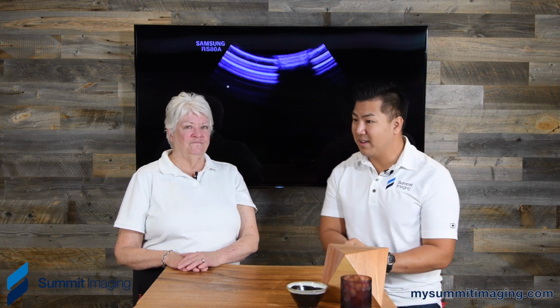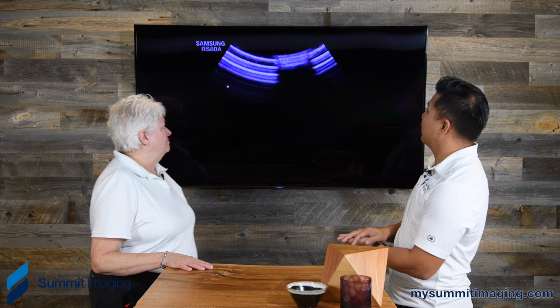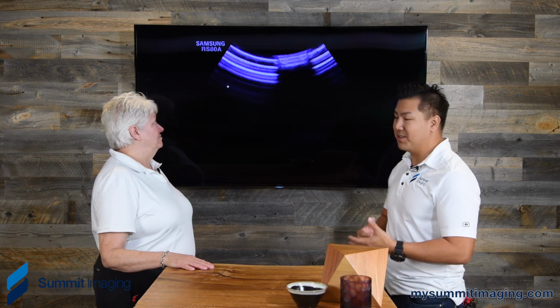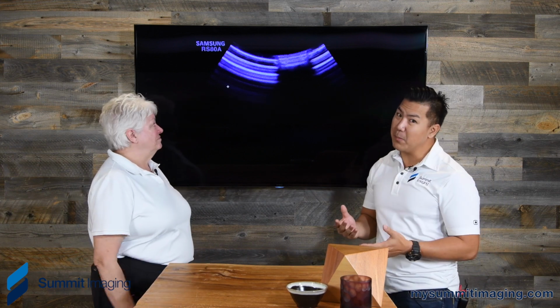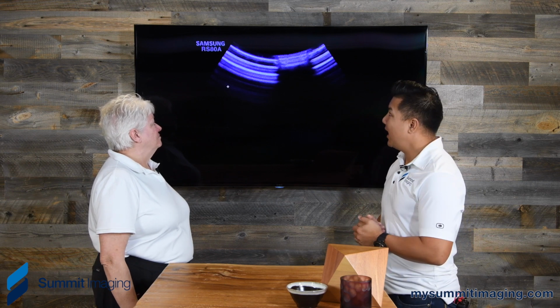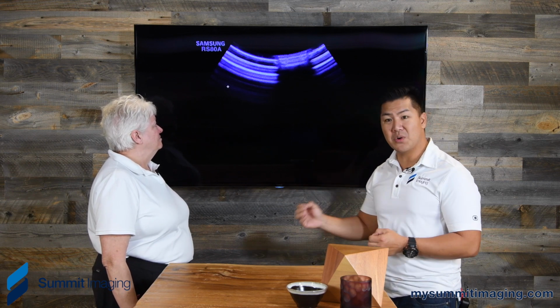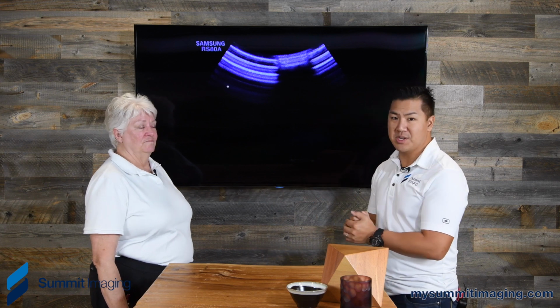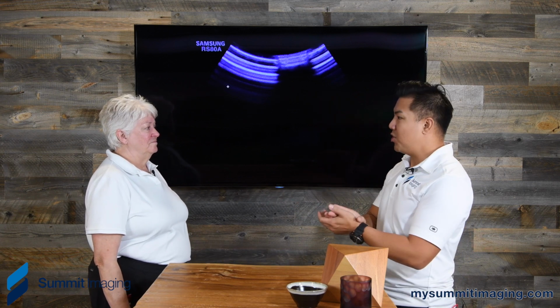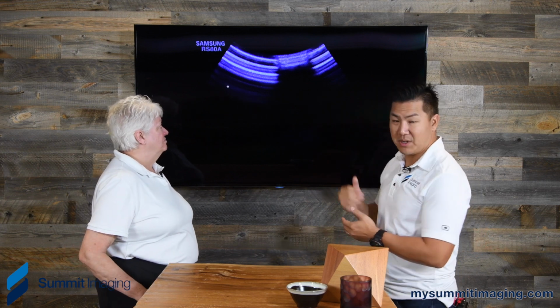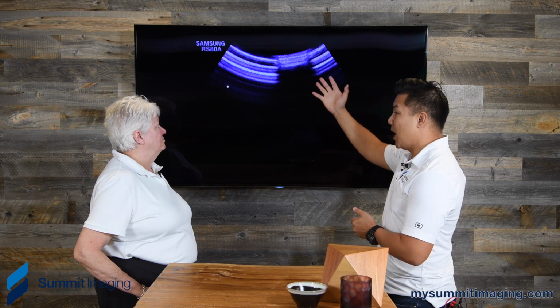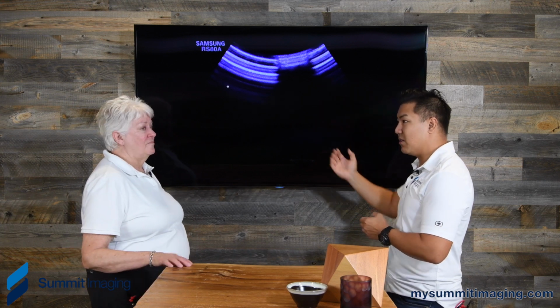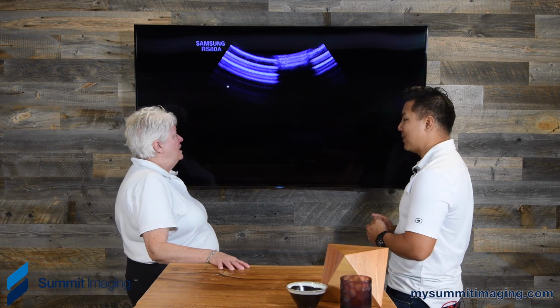And so today we're going to talk about, in particular, a massive drop. And this drop is actually fairly common for a particular transducer. It's a mechanical or volumetric transducer, which is the transducers that have domes. Those domes have a crystal inside, and they physically sweep back and forth, and it compiles a 3D or 4D image for the patient. But this is a common failure. So let's talk about the issues here first before we dive into the mechanics.